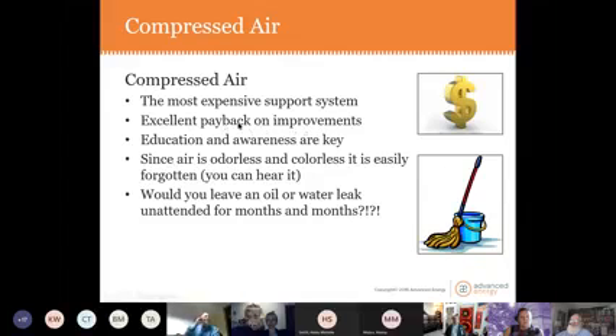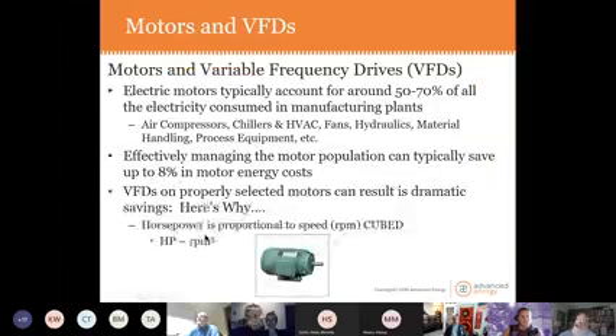You can get excellent capital paybacks on capital projects, but repairing leaks is almost free and almost has an immediate payback, fixing leaks. One thing to think about, air is odorless and colorless. So if it's leaking, you can hear it. If it's a big leak, you'll hear it. But if you have a water leak or an oil leak, that's going to go out on the floor and make a big puddle, and everybody's going to see it and mop it up. But you would never leave an oil leak or a water leak unattended for months and months because it's in the middle of the floor and everybody sees it. Air leaks kind of get forgotten because they don't see them and they don't smell, and there's not a mess, but they are very, very expensive.